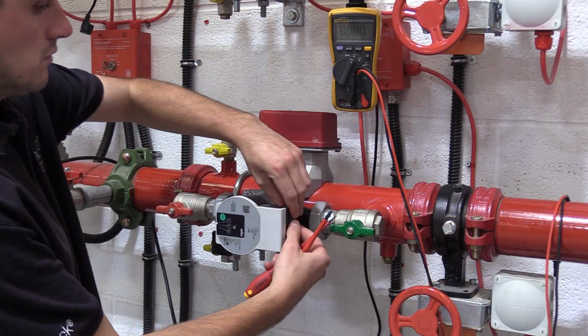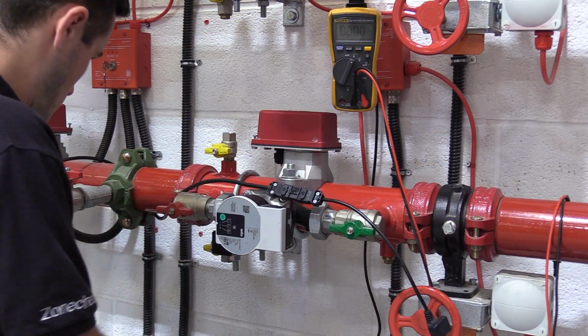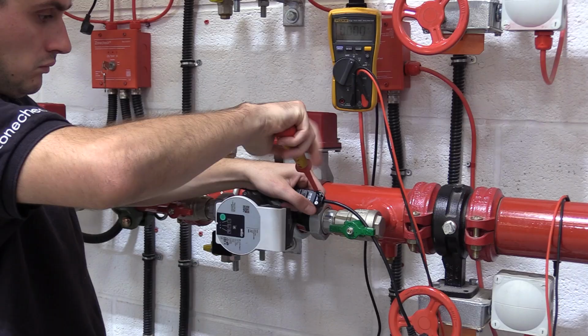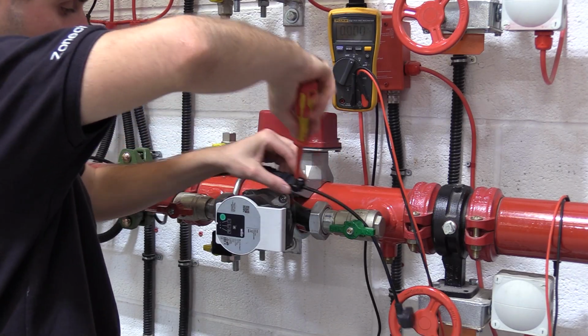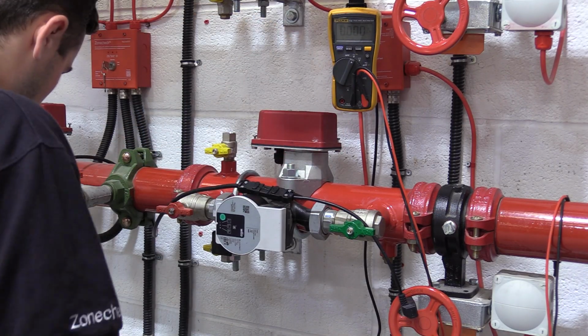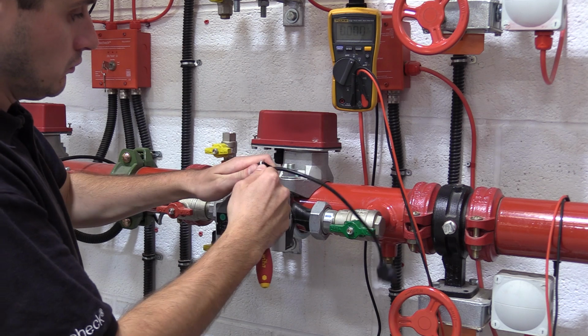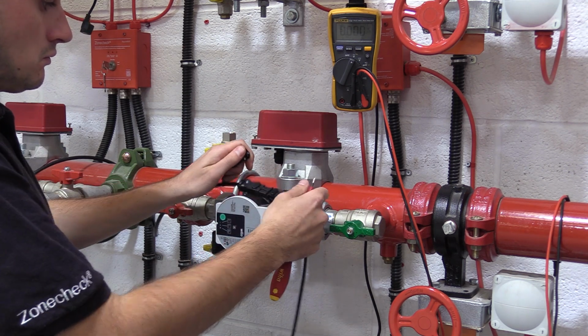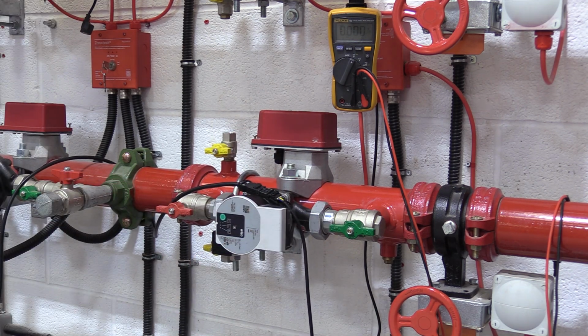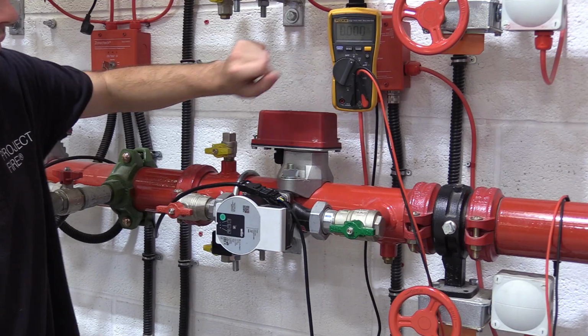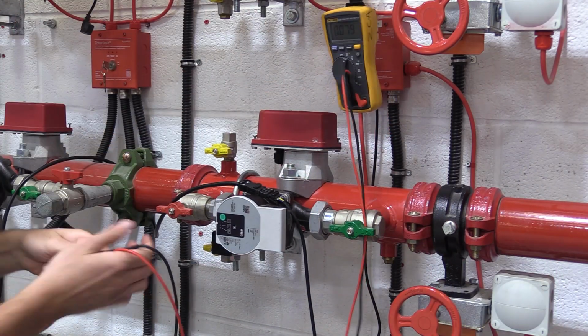Dead testing, continuity testing, voltage testing. Ensuring you have the correct electrical competency and safety in place. Use a multimeter or suitable alternative. Check for continuity between the key switch and the pump. Also, check that the voltage received by the pump is within tolerance.